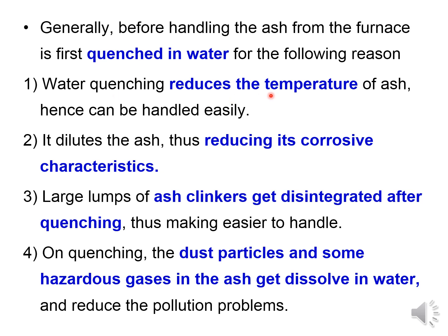Water quenching reduces the temperature, hence it can be handled easily. It dilutes the ash, thus reducing its corrosive characteristics. Large lumps of ash clinkers get disintegrated after quenching. Dust particles and some hazardous gases in the ash get dissolved in the water.